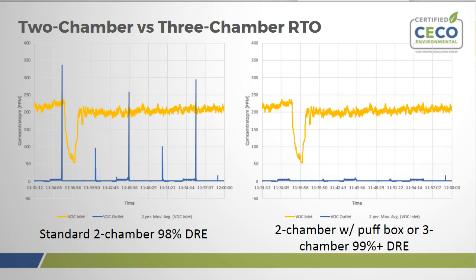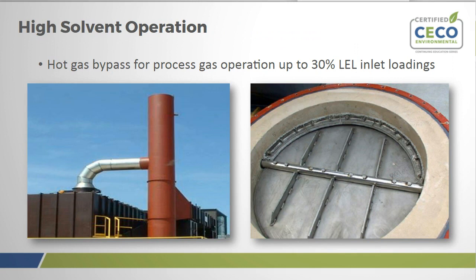Additionally, a really important, really cool feature, kind of a simple solution, but it works really well. I was explaining how the RTO requires very little heat to stay at temperature, right? But if you have a lot of process VOCs, or a very variable process where you have a little VOCs at a time but then some spikes, and you have to operate the oxidizer all the time, you would want to install hot gas bypass. It essentially derates the thermal recovery of the unit. There's a refractory-lined damper in the combustion chamber somewhere. It routes to the exhaust stack or the exhaust manifold, and it pulls hot air out of the unit. So this allows you to operate at very high LELs with the RTO. And anytime you're operating in this zone, the RTO has enough heat to get by.